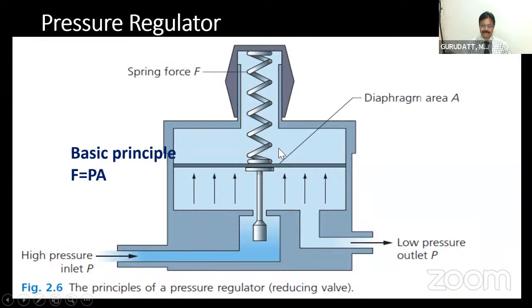I am showing you a simple diagram of a pressure regulator. Here you can see a spring force is there. This is a very high force that is always kept constant. Now the gases from the cylinder are passed through a smaller chamber next to a larger chamber. Once they enter the larger chamber, they encounter a large surface area of the diaphragm, so because the area is increased, the pressure automatically has to drop, provided the force is kept constant. Here the force applied is very high and always kept constant, so the outlet pressure always remains low.